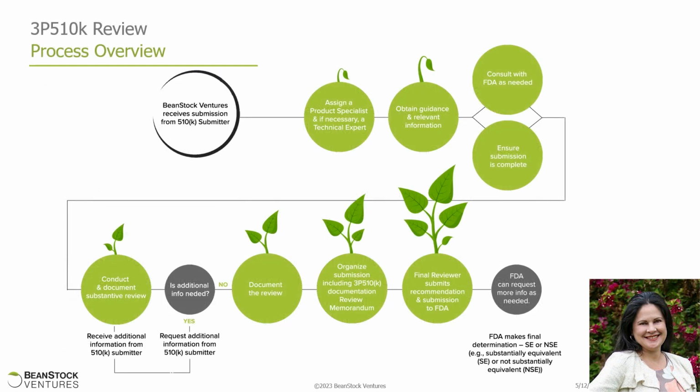The 510K review process is very similar to the traditional 510K process. The third-party review organization would receive your submission directly through eCopy or through eSTAR. They would then assign a project specialist, and if necessary, depending on your submission and the complexity, a technical expert. Then they'll obtain guidance and relevant information by consulting directly with the FDA. So the third-party review organization still interacts with the FDA.